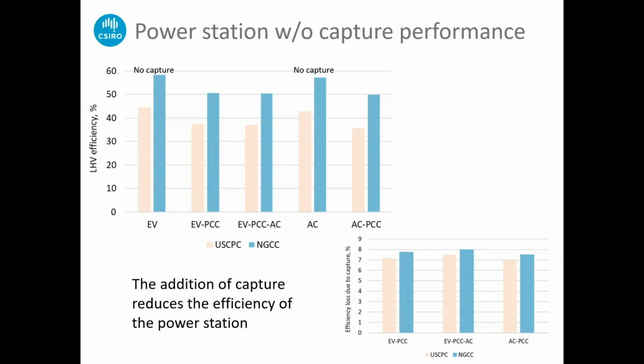As you see, obviously, when you attach a PCC plant to the coal-fired power station and the natural gas-fired combined cycle, it will lead to a reduction in output. The graph in the right-hand corner shows that that reduction is between 7 and 8% across the board for all of these power stations. But the air-cooled power station already starts off with a lower efficiency because of the higher condenser temperature, and also there's quite a bit of electricity going into the fans that we need for the air cooling system, and that typically gives you an efficiency hit of between 1 and 2% compared to evaporative cooling.